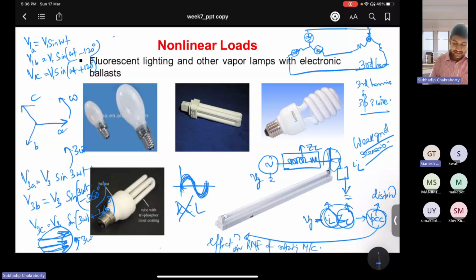That is clear. So now fifth harmonics. What is the fifth harmonics? How will they look like? If this is the fundamental ABC rotating in anti-clockwise direction in ABC phase sequence, how will the fifth harmonics look like? Fifth harmonics means 5 omega. So if it is 5 omega, then the minus 120 will become plus 120. If you multiply 120 with 5, as we did for the third, it will rotate in the opposite direction. And the seventh will rotate in the same direction as that of the fundamental. Hope these concepts are clear with you.